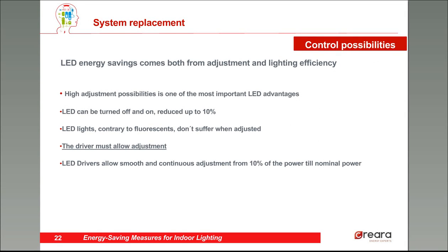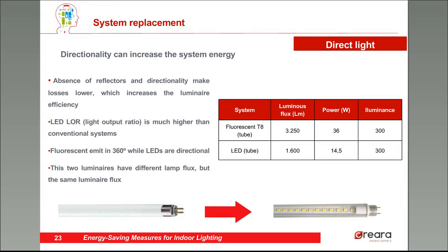Another advantage of LEDs is control possibilities. The great advantage of LEDs is that they don't suffer when adjusted, contrary to other lamps like fluorescents, whose lifetime is reduced when frequently turned on and off. LED power, and of course the luminous flux, can be reduced down to 10% of the nominal power. So it's really important to choose a driver that's compatible with regulation — otherwise we're not gaining one of the most important benefits of LED lighting.